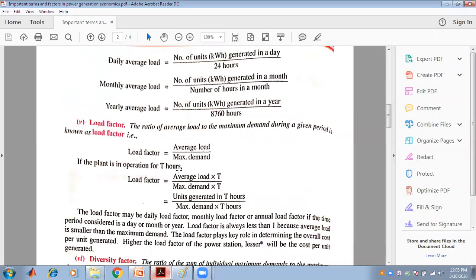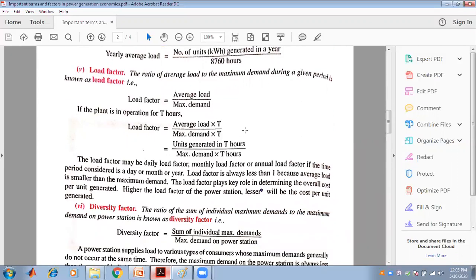The load factor is the ratio of average load to the maximum demand during a given period. If the plant is in operation for t hours, then load factor equals average load multiplied by t divided by maximum demand multiplied by t, which equals units generated in t hours divided by maximum demand into t hours. The load factor may be daily, monthly, or annual. Load factor is always less than 1 because the average load is smaller than the maximum demand.